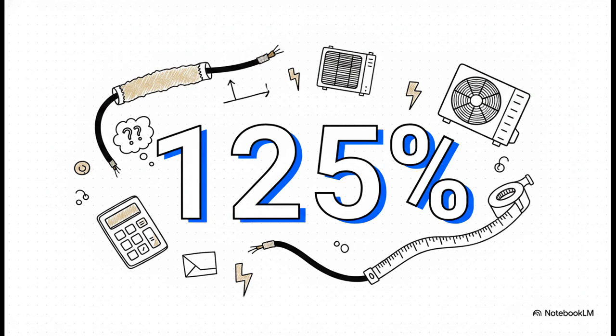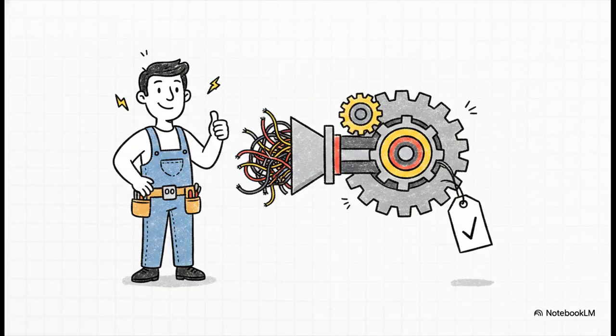Now, if you know the NEC, you know it requires branch circuits for AC equipment to be sized at 125% of the rated load. When you hear that, it sounds like you're about to be doing some serious, intimidating math to figure out your wire size. You're probably dreading busting out a calculator on a hot job site to do fractional math, right? Well, here's the massive relief. Your job is not to recalculate. Your job is just to verify. With modern AC equipment, the manufacturer has actually done the heavy lifting for you. They've already run that 125% calculation. And the result? That's exactly what's printed as the minimum circuit ampacity, the MCA, right there on the nameplate. So when you read that MCA value, you can rest easy. The 125% rule is already baked right in.